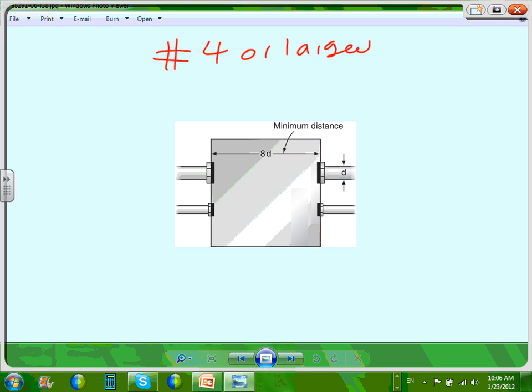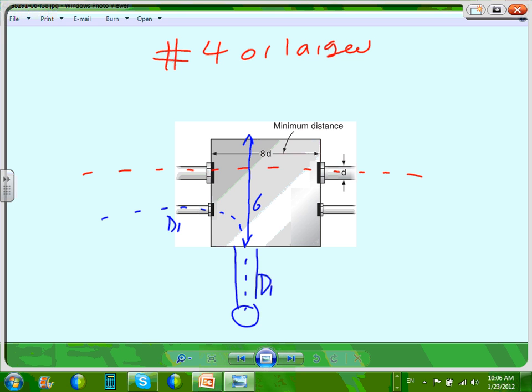And for the pull box, there are rules, if you guys remember. If you're pulling the conductors this way, the conduit, this size becomes 8 times the diameter. Can you guys see that? If you're pulling a straight pull, 8 times the diameter, right? Piece of cake. If I'm doing an angle pull, like we did last time, we don't have an angle pull here. Let's say there's another conduit here, and I'm doing an angle pull. Then this distance here, let's just say this conduit is D1, and this is also D1, the same size. This becomes 6 times D1, and also this becomes 6 times D1.